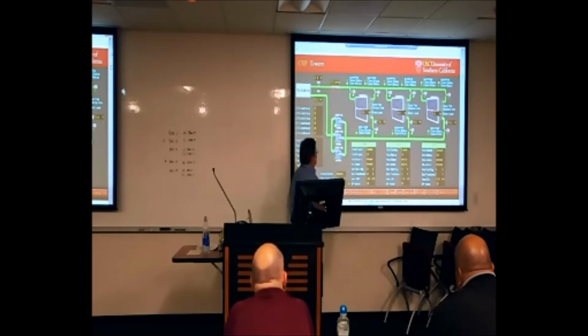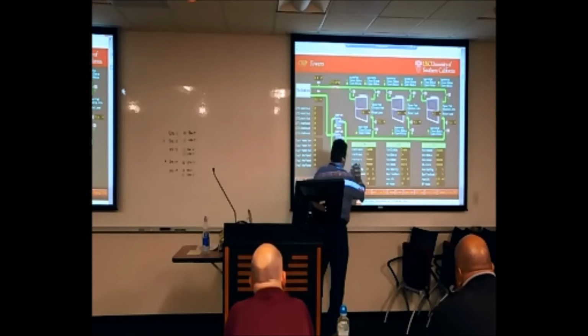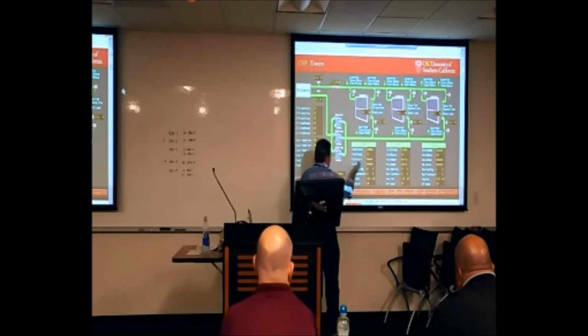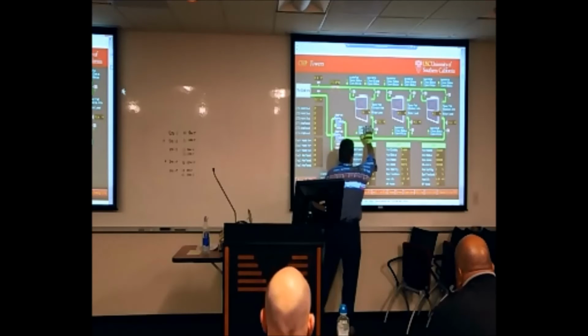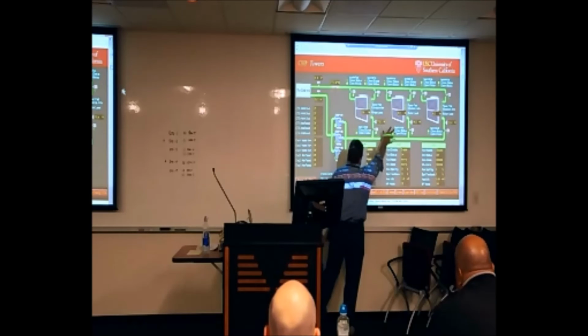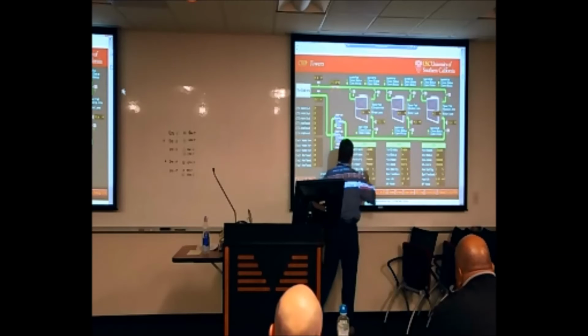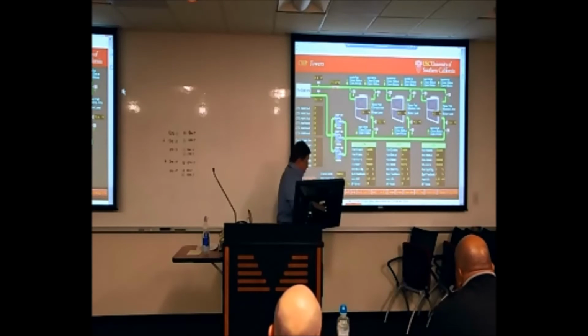The other failure is a VSD failure on the drive. So if the drive gets a VSD failure right here, we're going to fail that tower. It's going to secure it and roll to the next tower. The other one is a vibration alarm. If we get that, all the valves in the tower will close. Well, it'll open up the next tower and get that into service. Then these valves are going to close, and this tower goes offline in a failure mode.